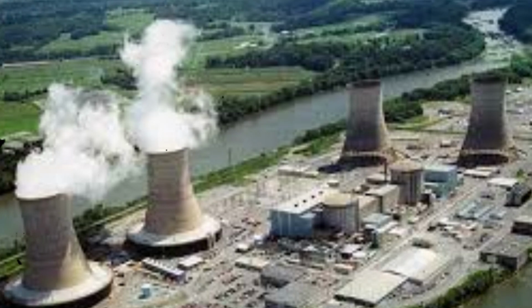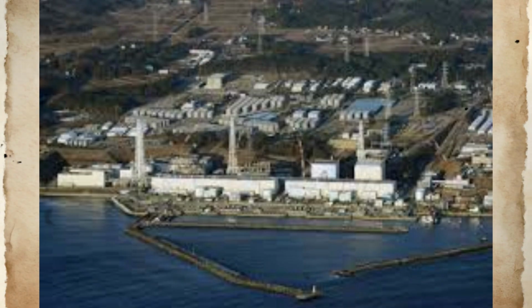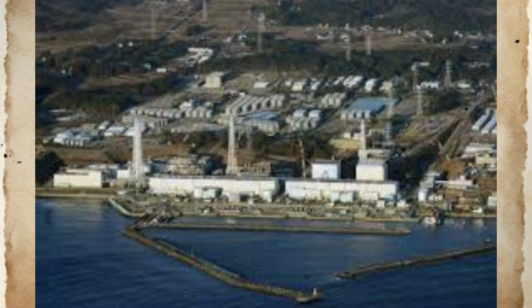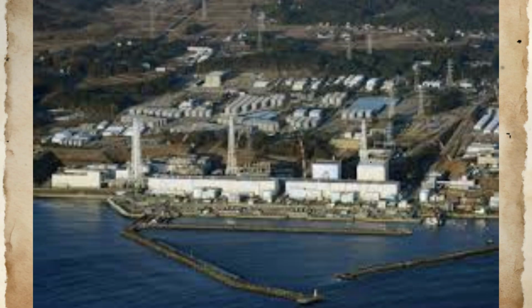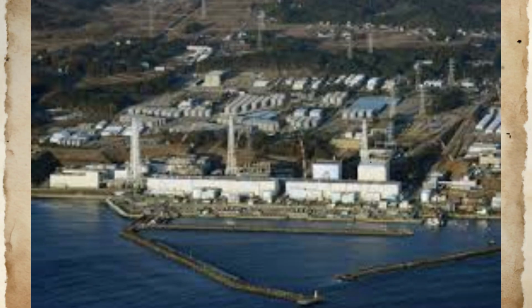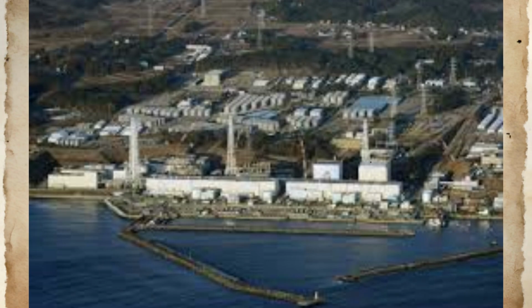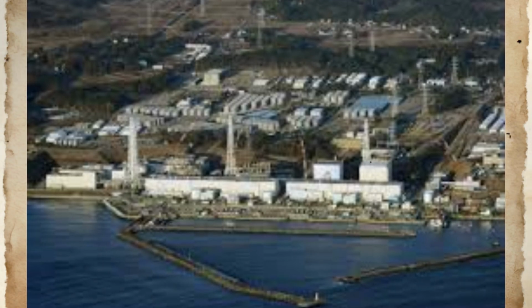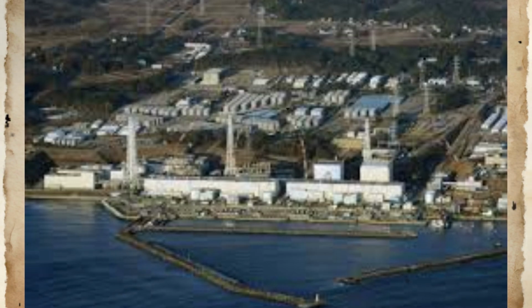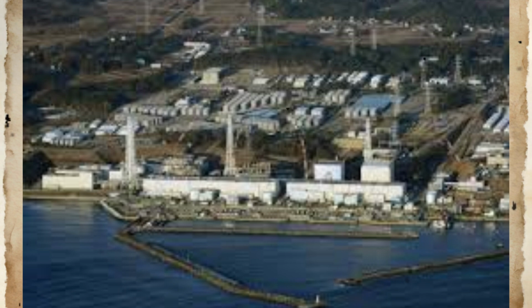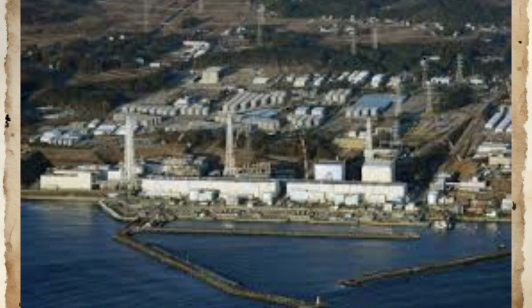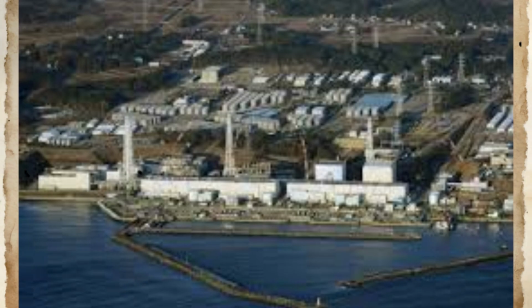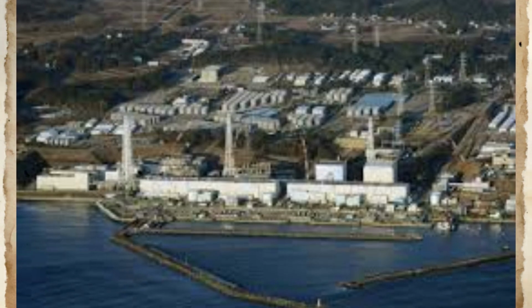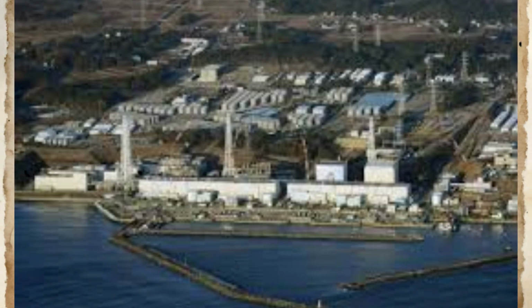These were rational engineering choices that improved plant operability and worker conditions during normal operations, which comprised 99.9% of the facility's operating life. The tsunami design basis itself had been established through a process that prioritized documented historical precedent over theoretical modeling. The Japan Society of Civil Engineers methodology, revised in 2002, relied heavily on historical tsunami records dating back several centuries. This approach provided quantitative confidence by anchoring estimates in observable data rather than computer simulations or theoretical maximum wave calculations. The resulting 5.7-meter design basis carried the credibility of empirical validation.